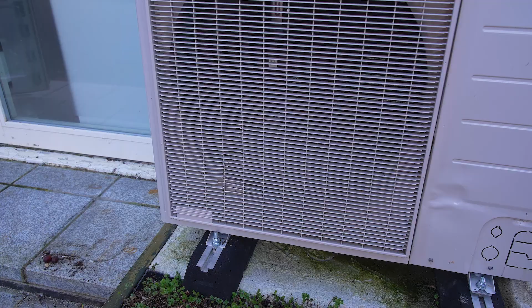How are you controlling it? You said you set the controller to 40 degrees. Yep. Where is that controller? The control interface is there, the brains is in that box. Right, so you've got a set flow temperature of 40 degrees. Yeah. Well, that's why you're nervous, because you're not using weather compensation. You set your flow temperature for what you want it at -2, and then for the rest of the year, as it's warmer, you should have a lower flow temperature continuously. That's how you get maximum efficiency out of this.